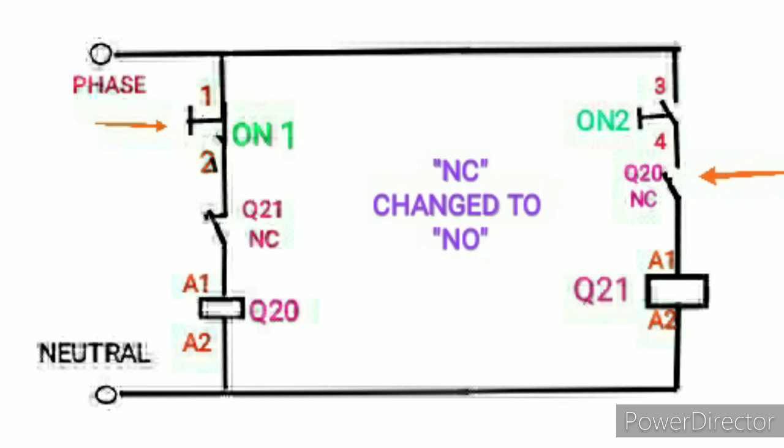So the auxiliary contact of Q20 also changed. Now see that NC changed to NO. So the contactor Q21 is not possible to operate because that interlock got opened. The NC is changed to NO.